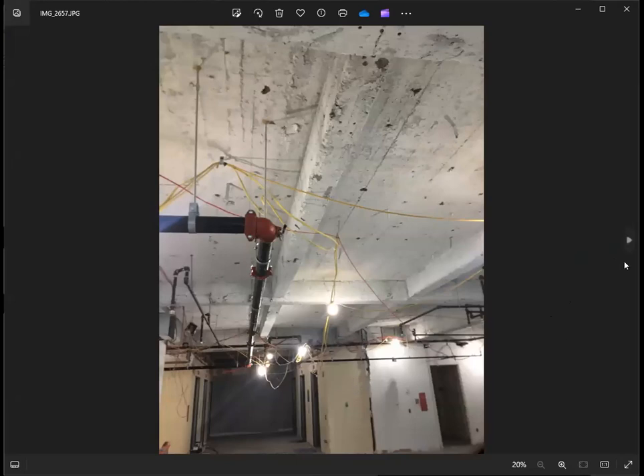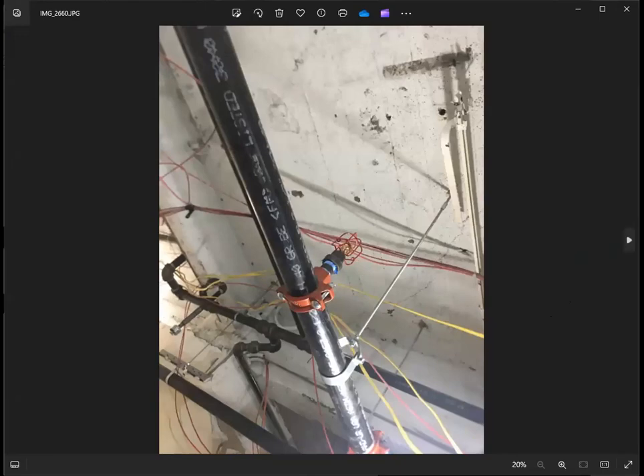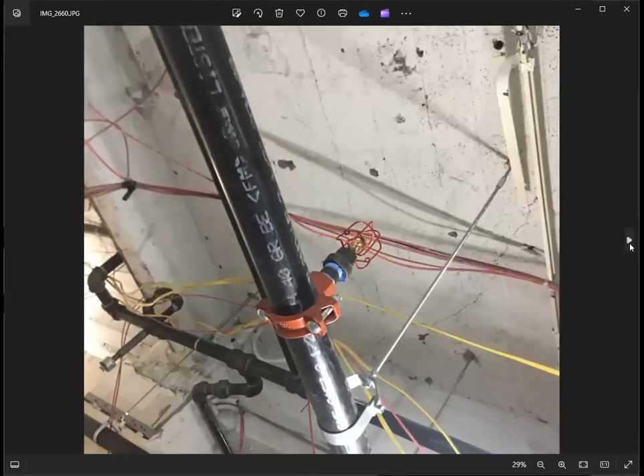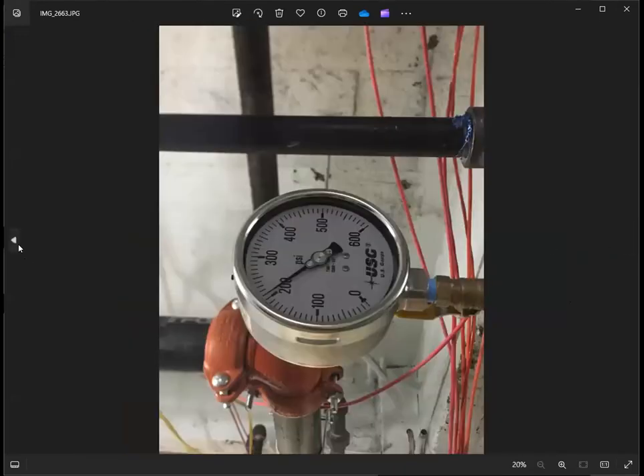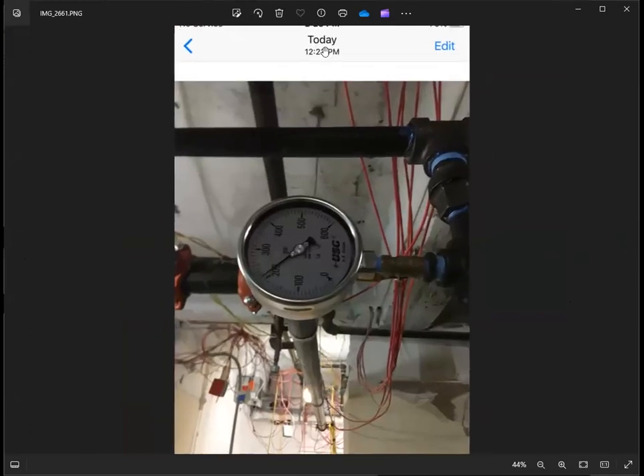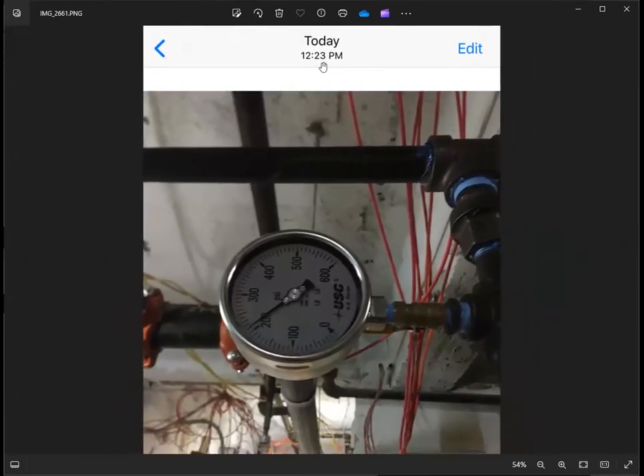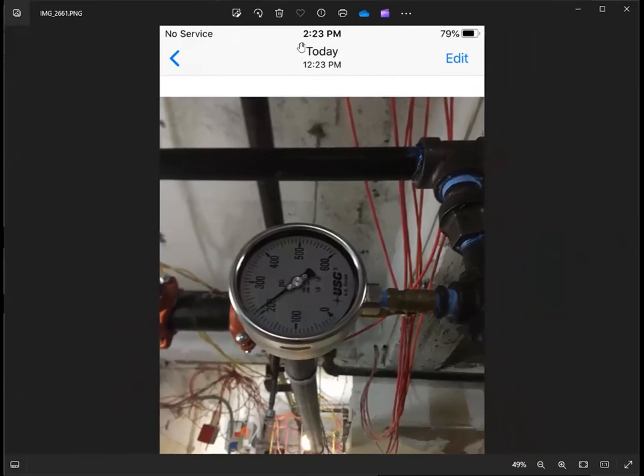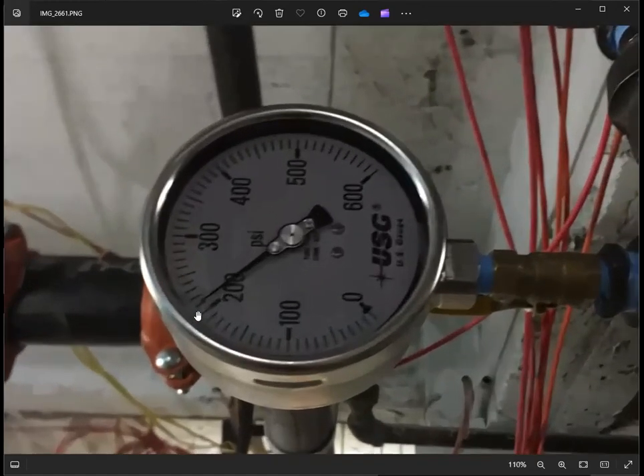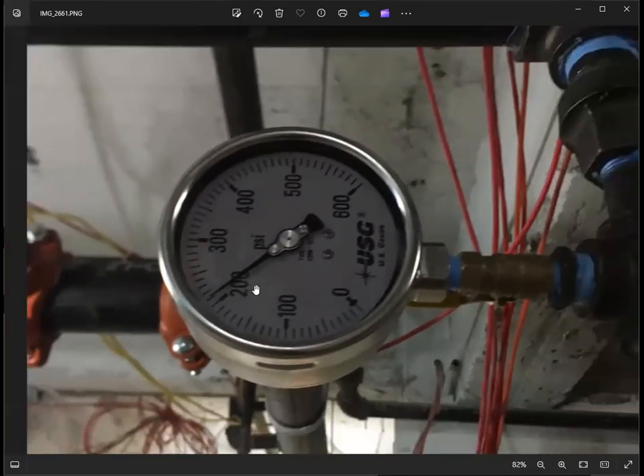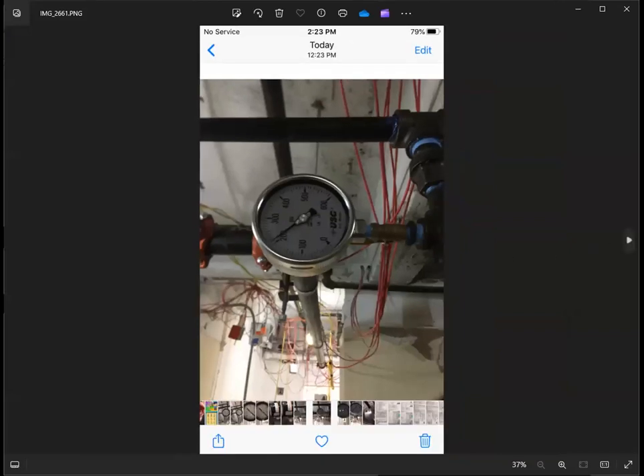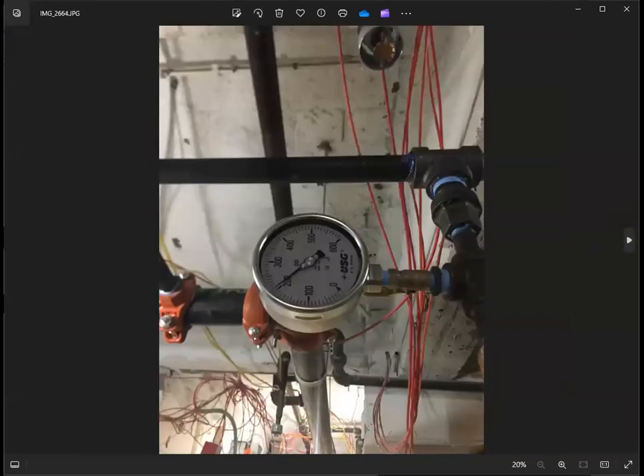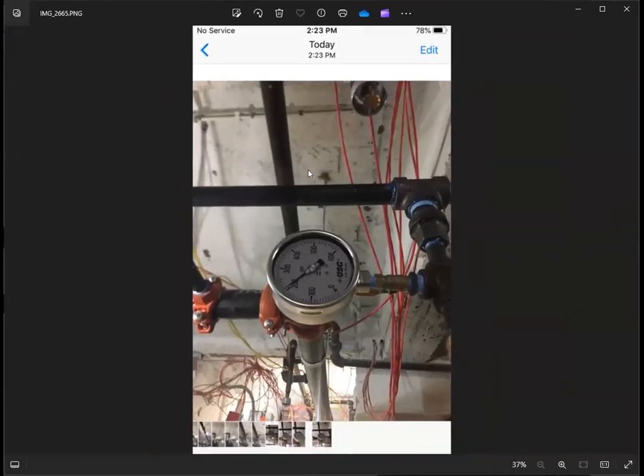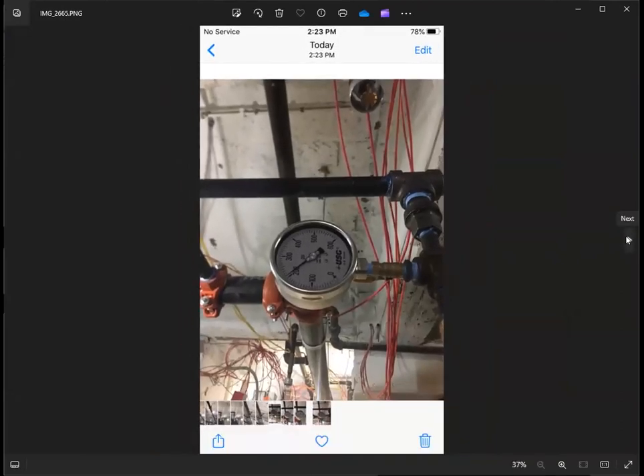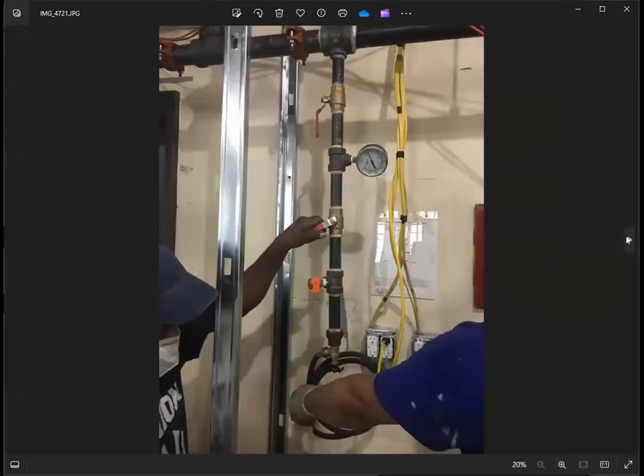So this is the whole job. They demolish everything. Schedule 40 black pipe. And here you go. So the test starts at 12:23 p.m. and I took a screenshot at around the 2-hour mark, 2:23 p.m. So make sure that the hand is still on the right position when you start the test. So that's how you're gonna identify a 2-hour test on your phone. Just have a screenshot after 2 hours.